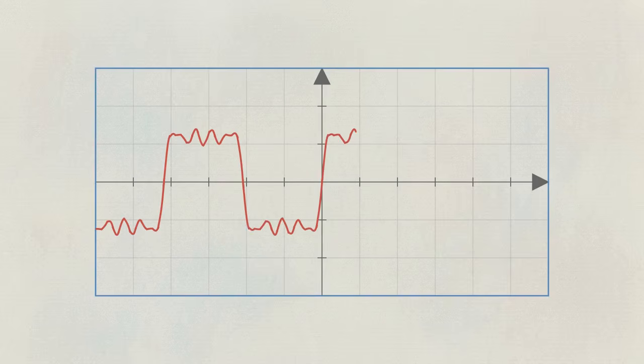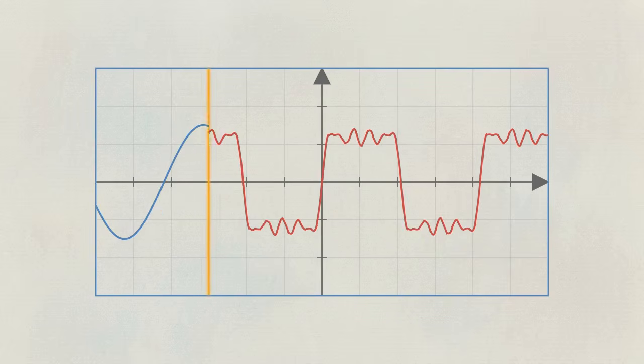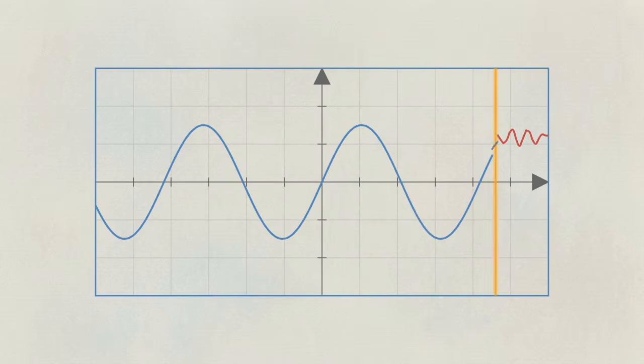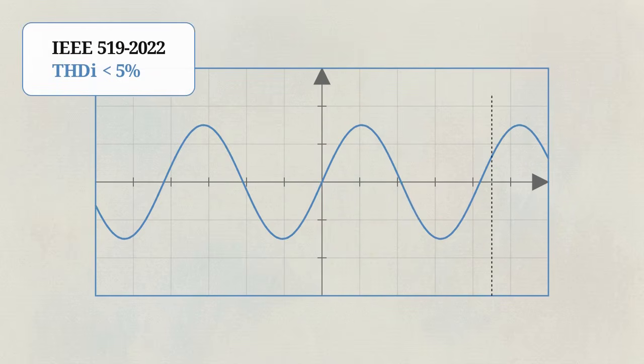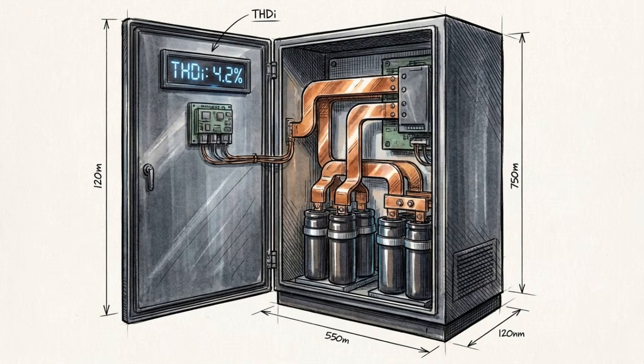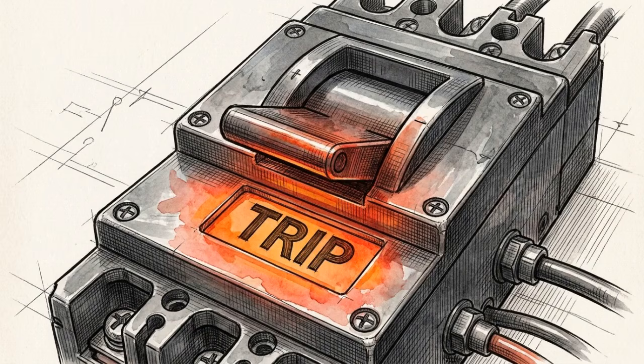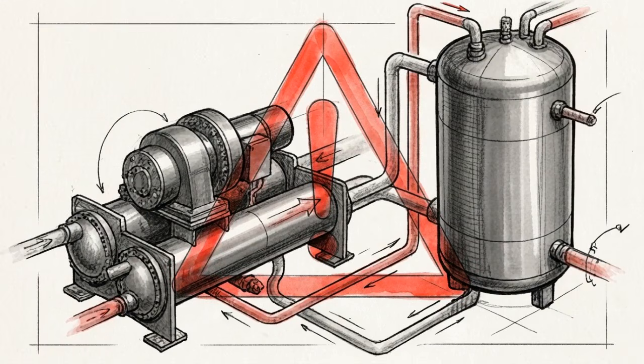The quality of that power is heavily scrutinized under the IEEE 519/2022 standard for total harmonic distortion, measured at the point of common coupling. Built-in active front-end variable frequency drives clean up the waveform, ensuring that harmonic distortion remains below 5%. Without this cleanup, dirty voltage distortion will prematurely trip the backup generator breakers. Mechanical recovery is entirely subordinate to power quality. Introducing highly distorted power during a massive plant restart will instantly abort the entire cooling recovery sequence.